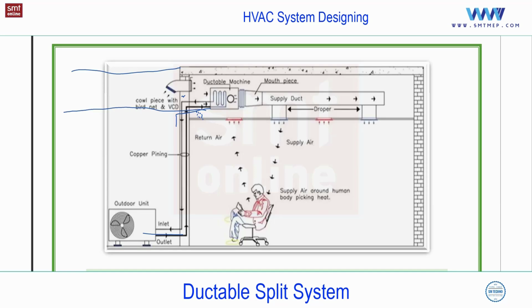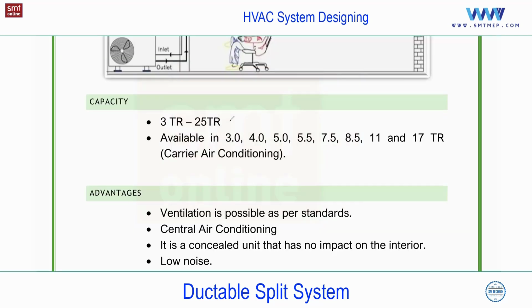And if this drain pipe is running above any electronic equipment, like suppose it is passing through the server room or any electronics, we require that the drain tray also be placed below the drain pipe for additional protection, with insulation. First, insulation on the pipe is required, then apart from this the drain tray is also required. And even if this unit is placed above any electronic equipment, below the unit also we require one drain tray for additional protection.